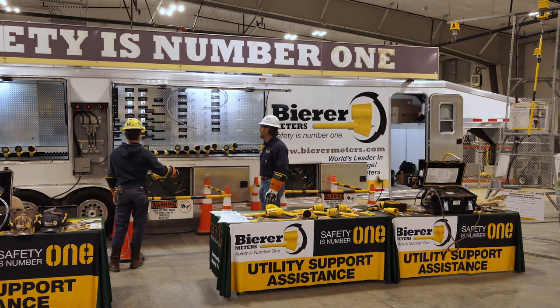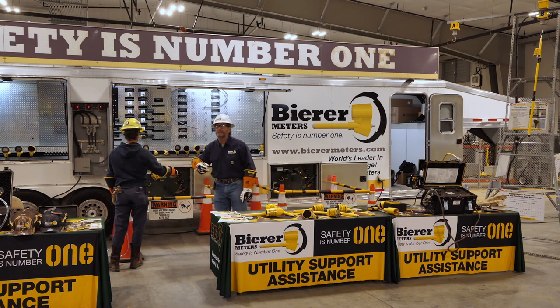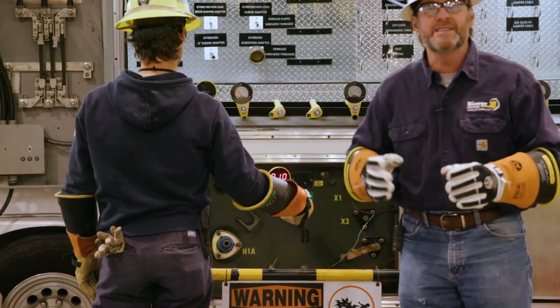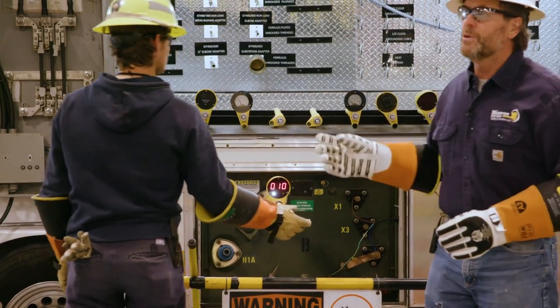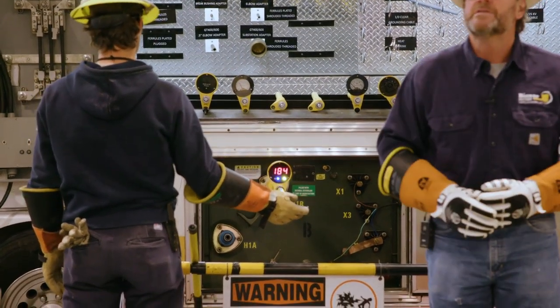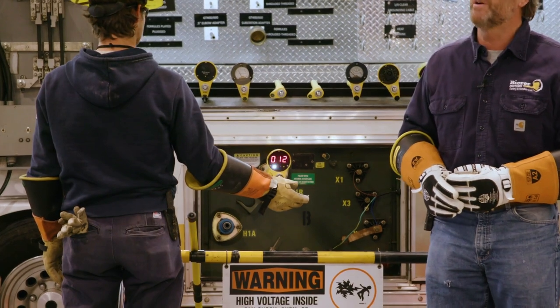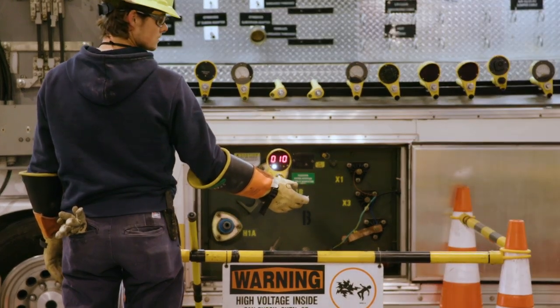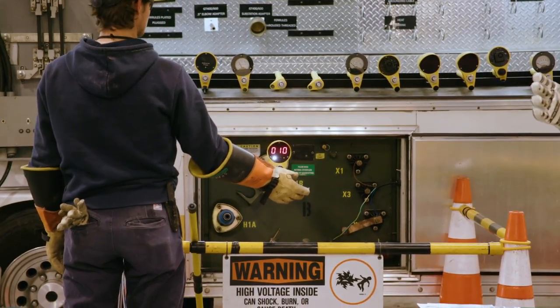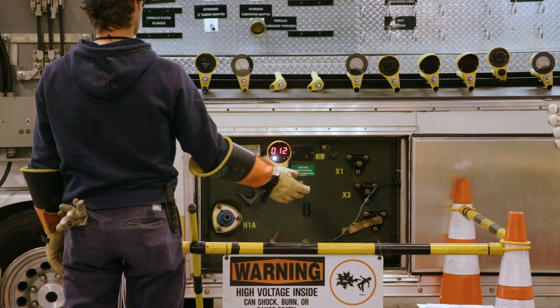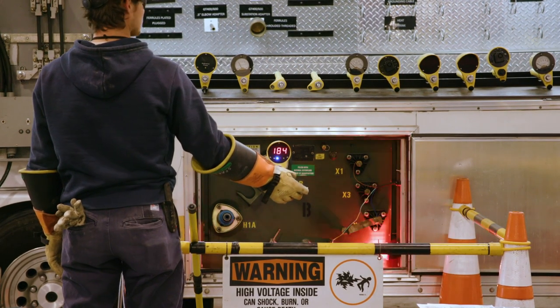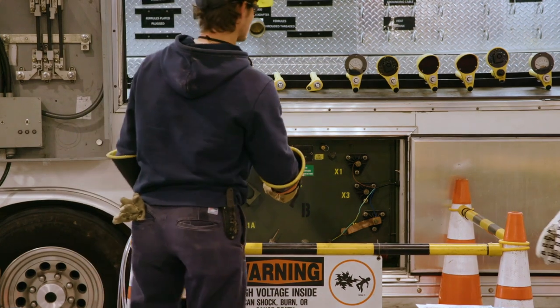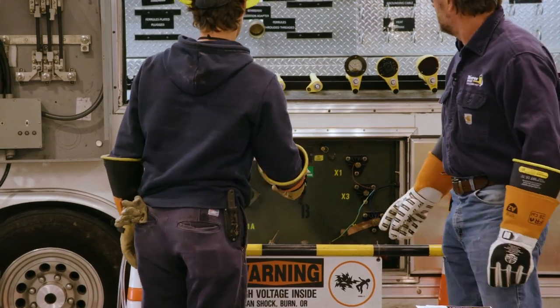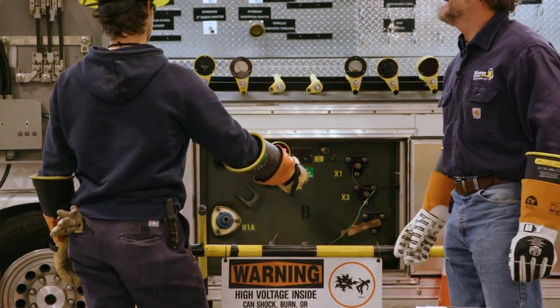Trying to get to a B phase, a reference phase. There you go. If you have trouble - I heard earlier at the last presentation that somebody was phasing a tight bolt and the tool was getting confused with some other sources because it was a very tight bolt. Use a zero ohm extension, take that meter head away from those other sources, it'll do better for you, okay? Okay, it's still getting a little confused, trying to say 180 out.